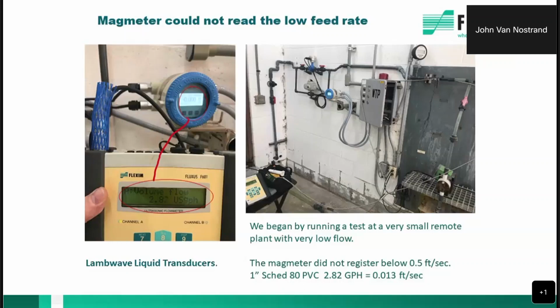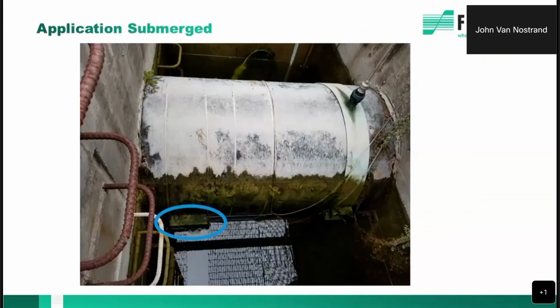So remember I said our low detection limit is 0.03. Well, we're at 0.013. So we're actually below our standard accuracy. We're essentially outside our range, but we're still able to measure. So measurement is better than no measurement for sure. Are we extremely accurate below our low limit detection? Our accuracy has that bell curve just like the Magmeter, but the point here is we're 100 times lower than 3 feet per second. So these are larger.